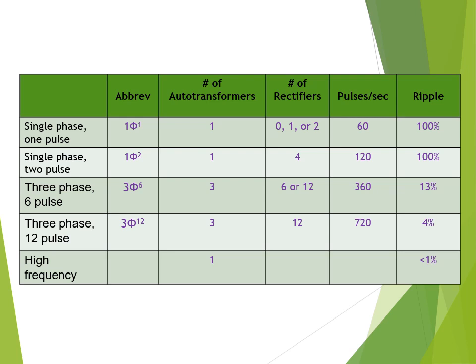The number of autotransformers for single phase and high frequency are 1, and for the 3-phase we have 3 autotransformers. For the single phase 1 pulse, which is half wave rectification, we have 0, 1, or 2 rectifiers. For single phase 2 pulse, which is full wave, we have 4 rectifiers. 3-phase 6 pulse, we have 6 or 12 rectifiers, and we have 12 rectifiers with 3-phase 12 pulse. We have 60 pulses per second for single phase 1 pulse, 120 pulses per second for single phase 2 pulse, 360 for 3-phase 6 pulse, and 720 for 3-phase 12 pulse. And then the ripples are the same for the single phase units. They're both 100%. It's 13 to 14% for the 3-phase 6 pulse, and 3-phase 12 pulse is 4%. High frequency has a ripple of less than 1%.